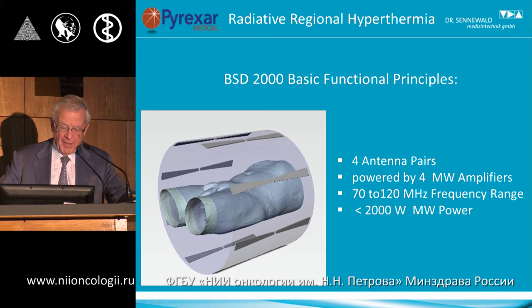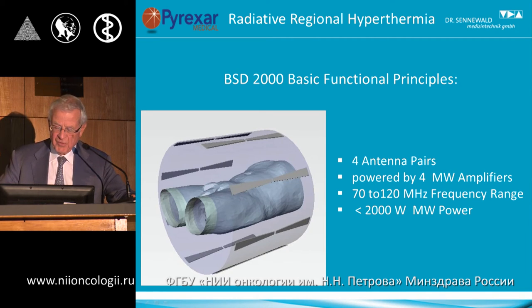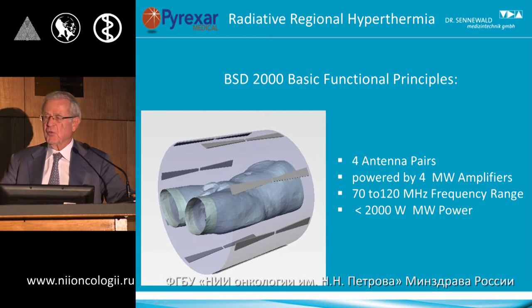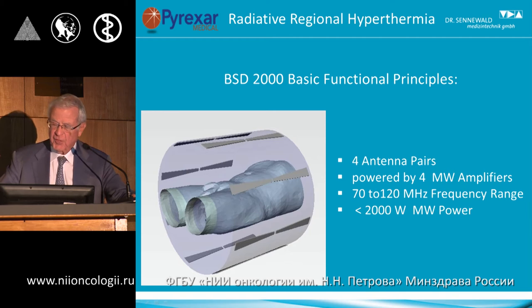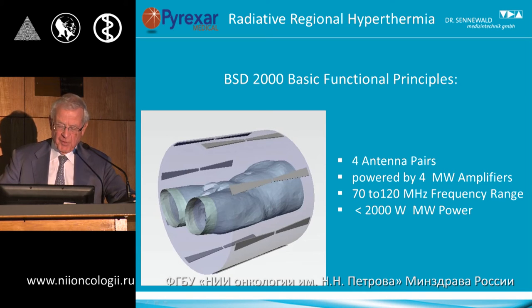Returning to the functional principles: four antenna pairs powered by four microwave amplifiers. The operational frequency range in this applicator — which has a diameter of 60 centimeters — is 70 to 120 megahertz. The power applicable through this applicator into the patient is up to 2,000 watts.